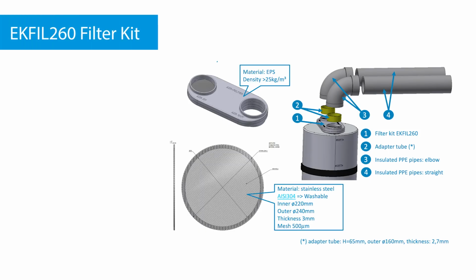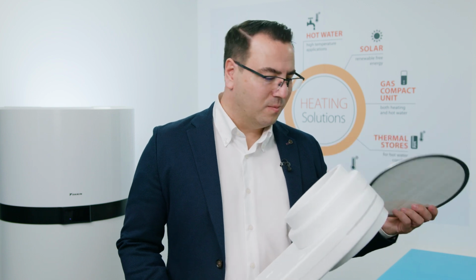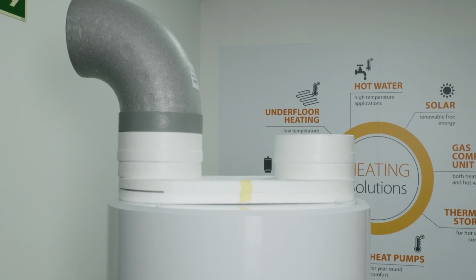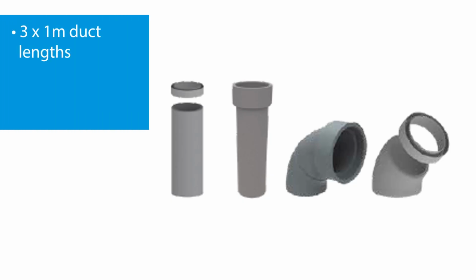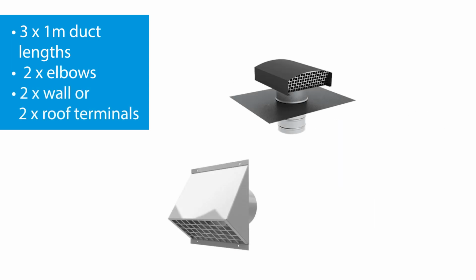To prevent the intrusion of foreign contaminants entering the heat pump, an optional filter kit is available for all heat pump models. On top of the heat pump is an oval-shaped adapter fitted with 2 cutouts in DN160 to connect onto the ducting. It is just 65mm high and 2.7mm thick. Inside is a stainless steel mesh with a diameter of 240mm and 3mm thickness, and it can be washed during regular maintenance. To complement the offering, a connection kit with wall or roof terminals is also available. The set consists of 3 duct lengths, 2 elbows, and 2 wall or roof terminals, depending on the choice. Unfortunately, clamps, fixing rods, and brackets are not provided. If extra components are required for the ducting, Daikin can offer them also.